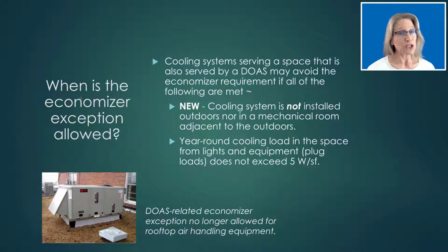So the year-round cooling loads in the space that the DOAS serves from lights and equipment cannot exceed 5 watts per square foot. So if you're installing a DOAS system that you're pairing with your heating and cooling system, and if it can meet both of these criteria, then you can take this exception for economizer.